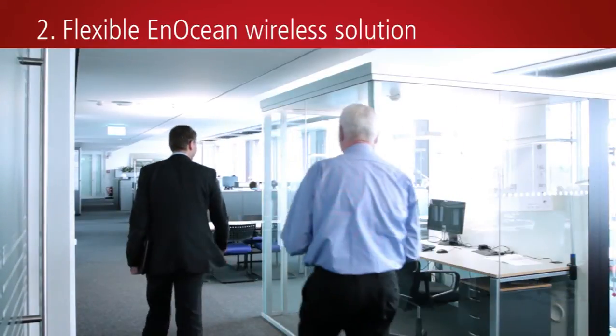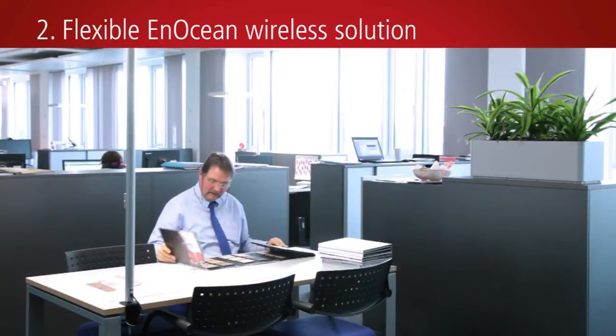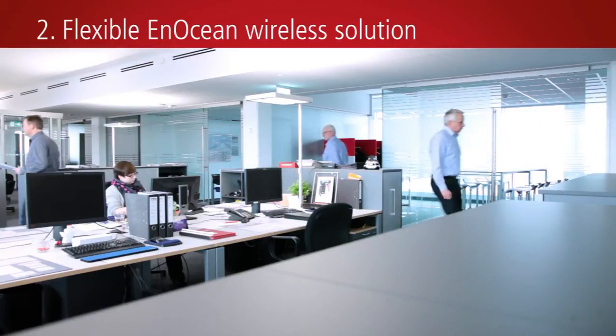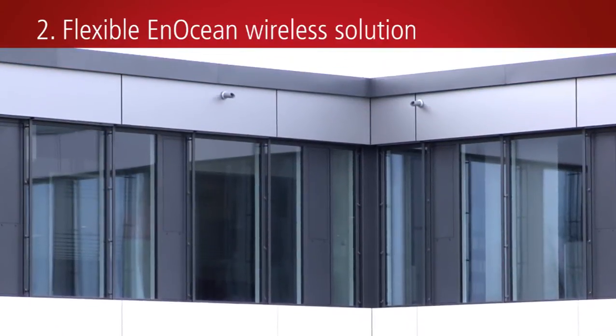The new open space concept meant that the floor plan didn't have to be finalized until a relatively late stage, a benefit which would have been very difficult to achieve with a wired installation. The elimination of cabling not only reduces costs, but also the fire loads associated with cables. With around 200 EnOcean control buttons on each floor, purely software-based commissioning significantly reduces the potential for error compared with conventional wiring.